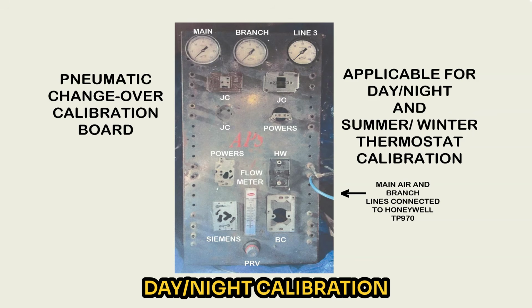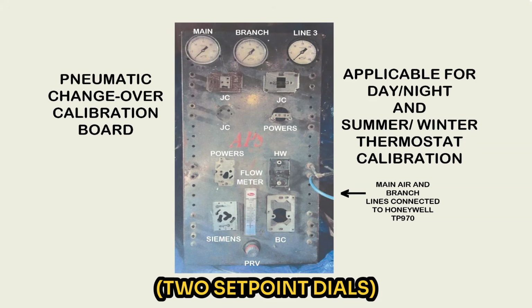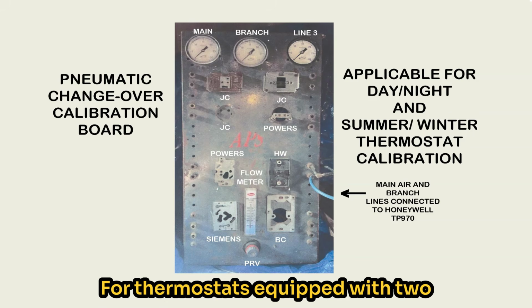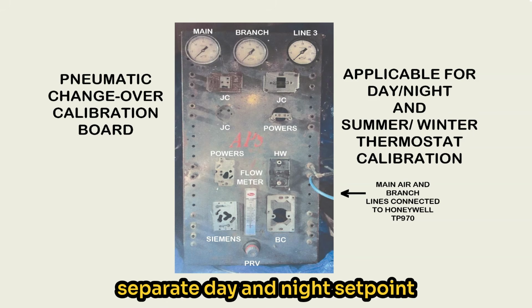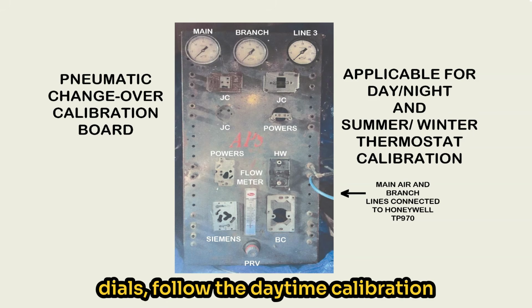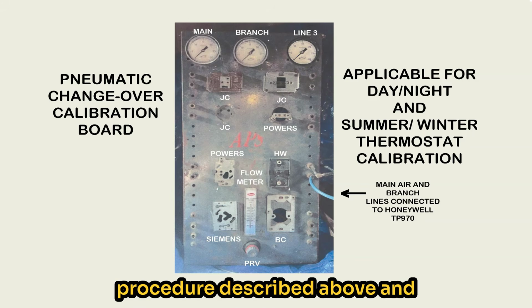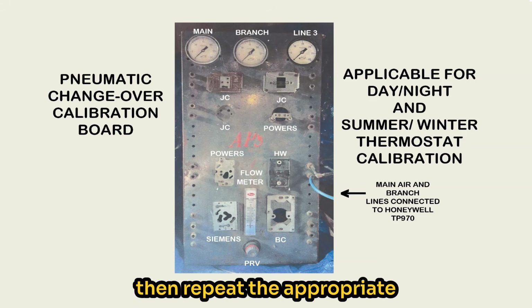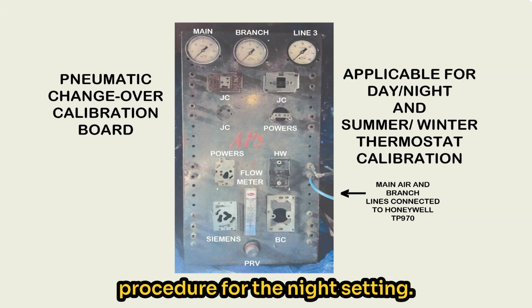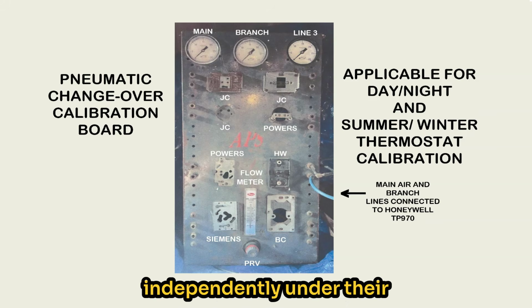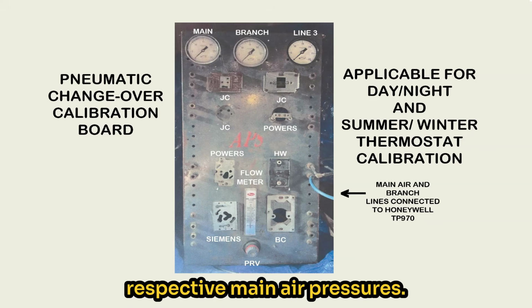Day-night temperature calibration, 2 set point dials. For thermostats equipped with 2 separate day and night set point dials, follow the daytime calibration procedure described above and then repeat the appropriate procedure for the night setting. Verify both settings independently under their respective main air pressures.